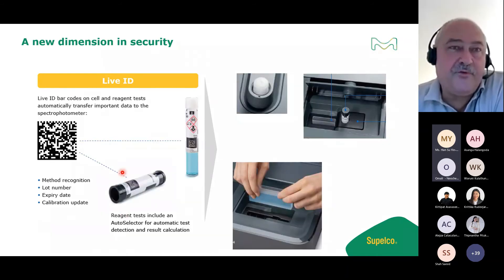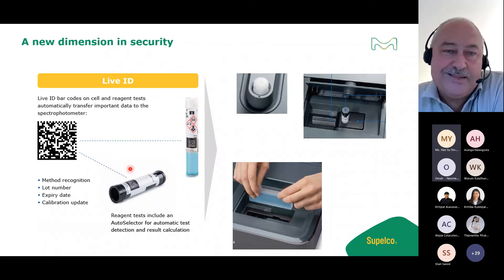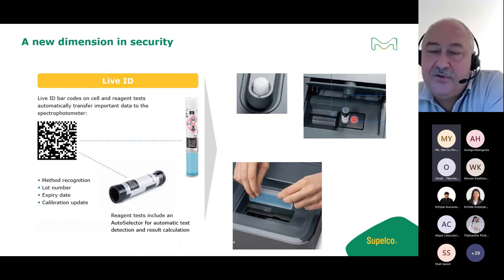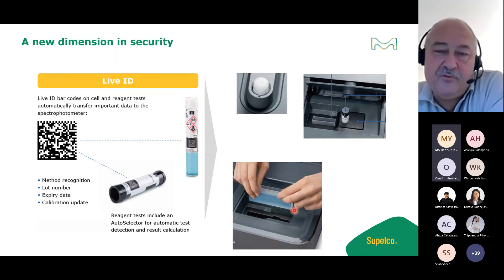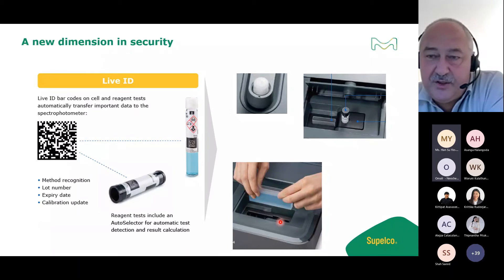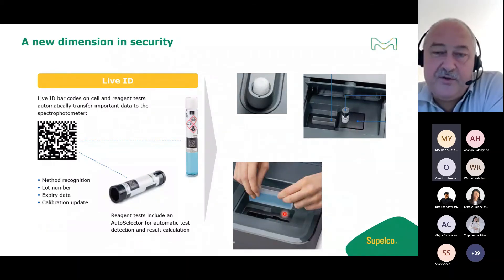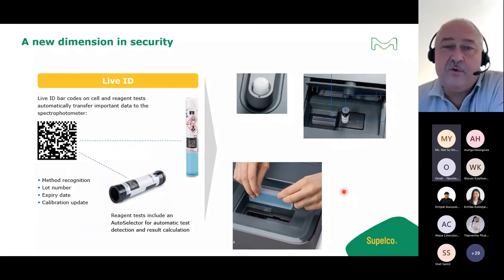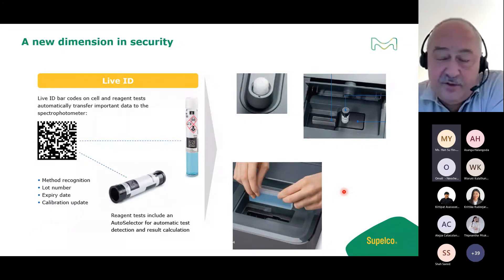The photometers are flexible: the 2D barcode on cell test kits and the auto selector enable automatic method selection. For the Prove 600, you can remove part of the shaft to insert 100 mm cells for ultra-sensitive measurements. A publication exists on ultra-sensitive iron measurement for drinking water using the 100 mm cell.